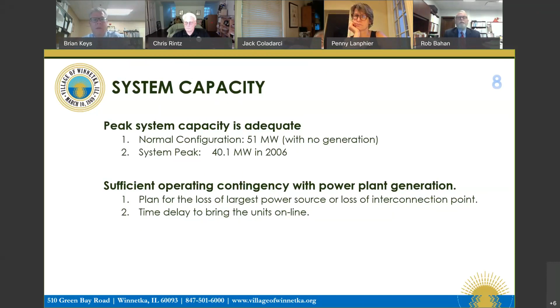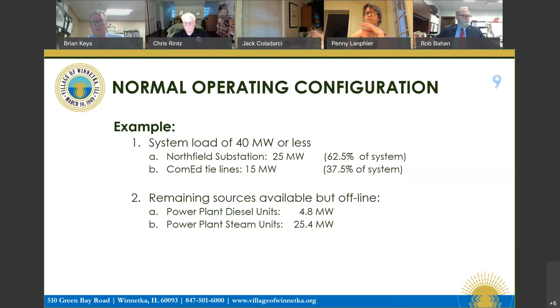Next slide, please. Generally speaking, on a day when we're at 40 megawatts, the load splits out so that we're bringing about 62% in from our Northfield substation and 37% from our ComEd tie lines. The generation is typically offline and available for dispatch for our localized emergencies. The 4.8 megawatts is available in a shorter period of time, at 90 to 120 minutes. The power plant, assuming we haven't been running and we're bringing it up cold, takes the longer 8 to 10 hours.